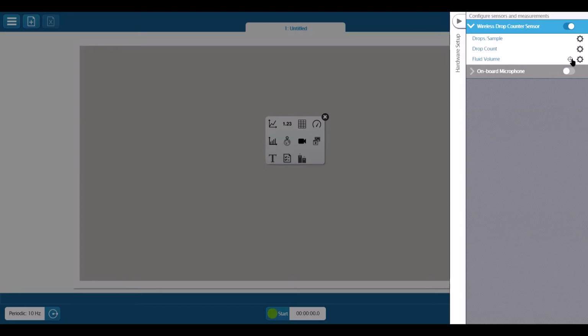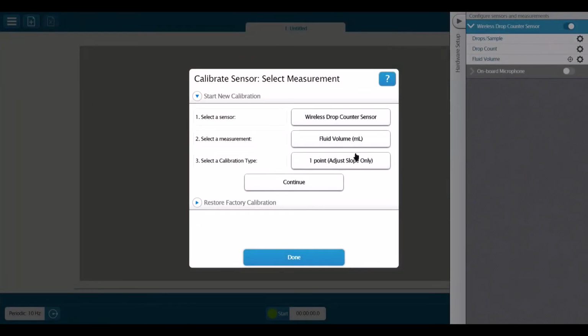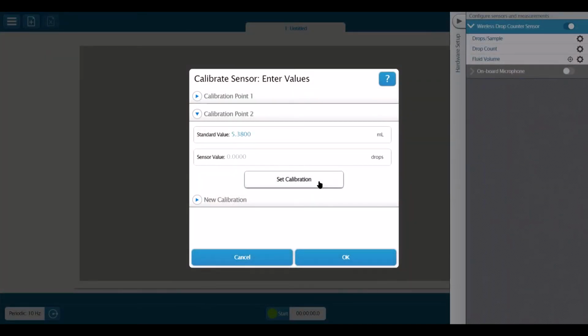Make sure that it says 1 point adjust slope only before clicking Continue. Then, make sure that the sensor value reads 0. If it has any other number here, then you need to exit the program and restart it and go through the whole software setup again. Once the sensor value reads 0, you can go back to your setup.